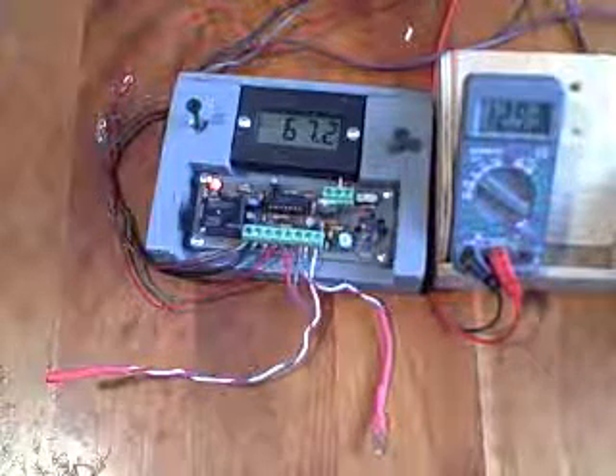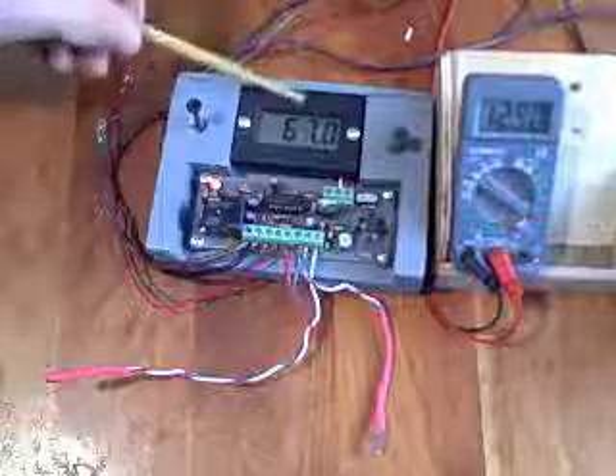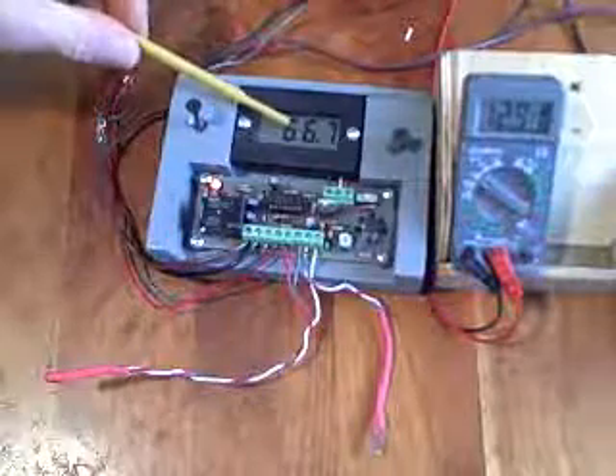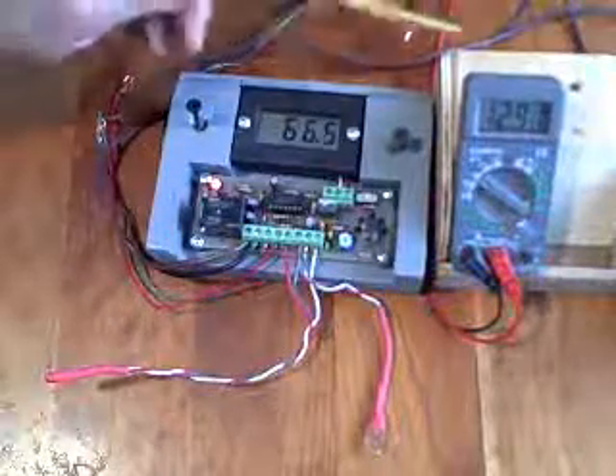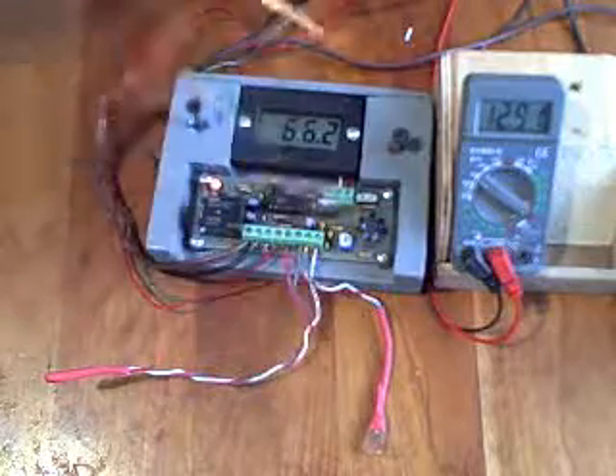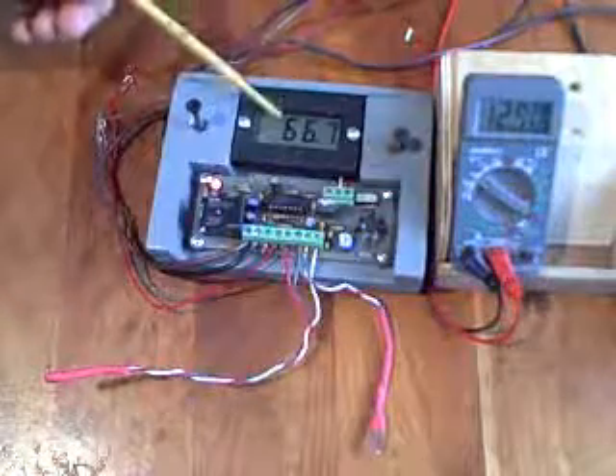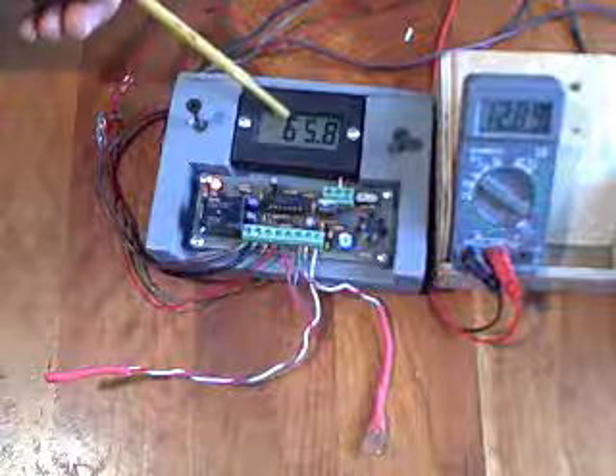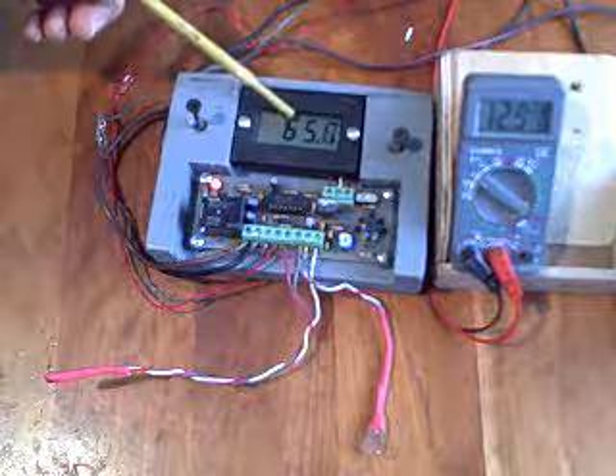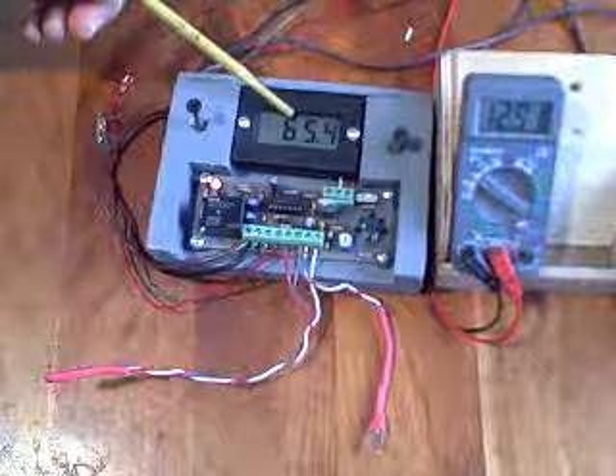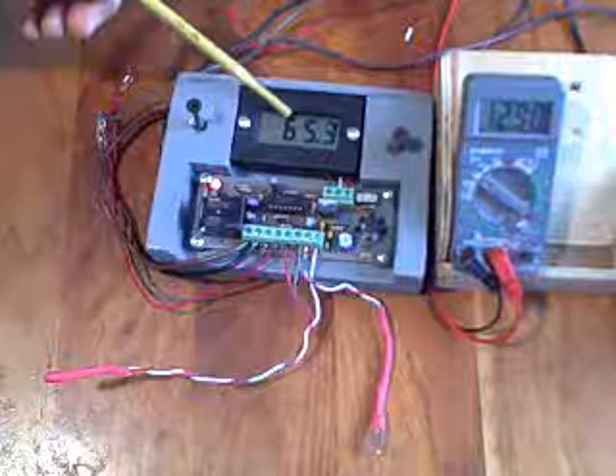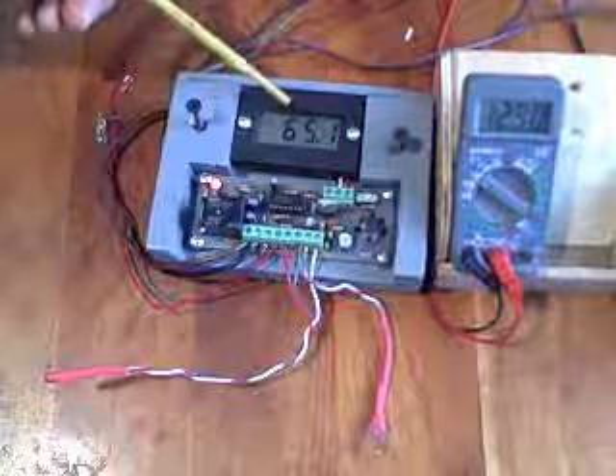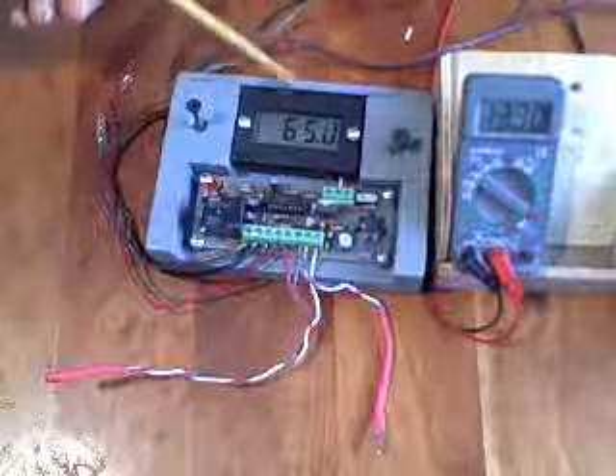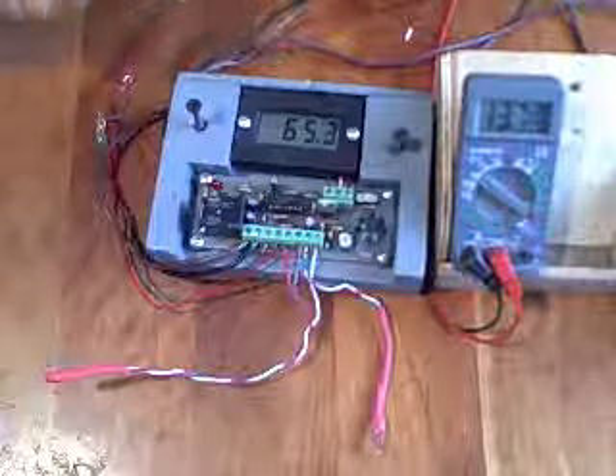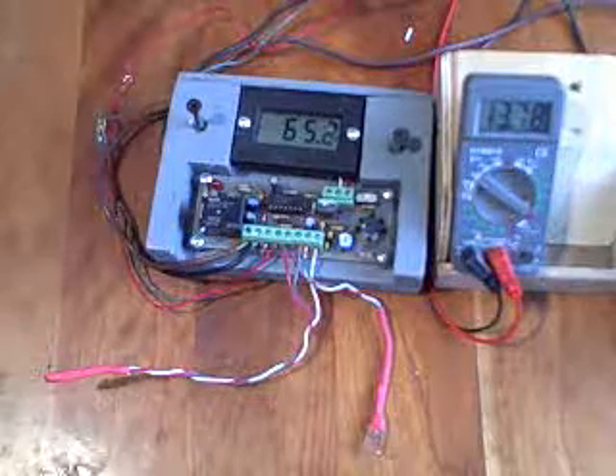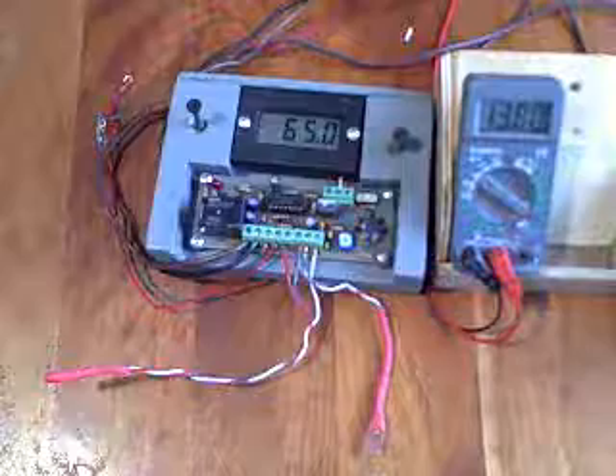Okay, so now the temperature in the collector is 67 degrees. Remember, the temperature in the tank was 64. So as this gets close to that temperature, it should eventually turn the pump off. Let's see. Okay, so at 65 degrees, the pump shuts off. Good, everything is working as it should.